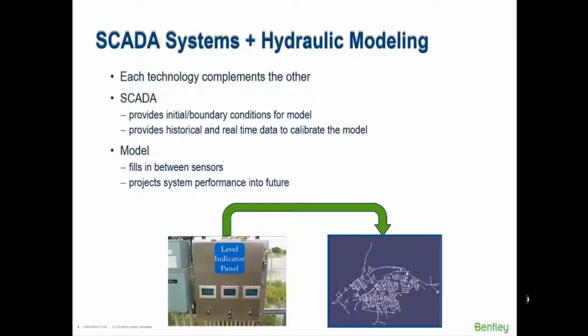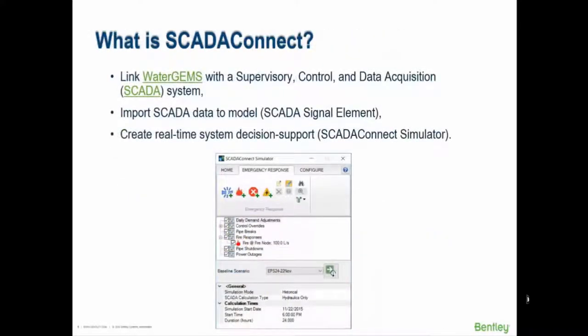So what is SCADA Connect? It's a general name for a couple of things. One is the ability to link WaterGems with the SCADA system and bring data into the model — such as initial tank levels or which pumps are running. But there's a bigger use called SCADA Connect Simulator, which gives the operator or someone who isn't a modeling expert a really simple user interface to make a quick model run based on a scenario you've provided as a base. There's a lot of value in this, including emergency planning, scheduling flushing, and modeling what happens when you take a tank out of service.